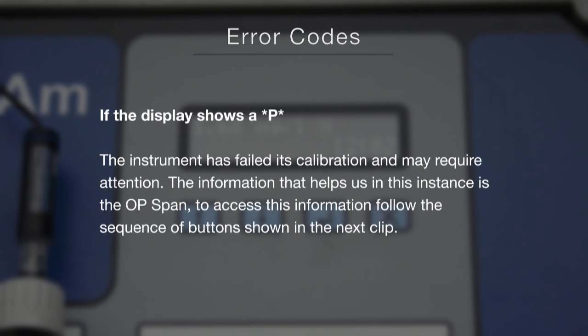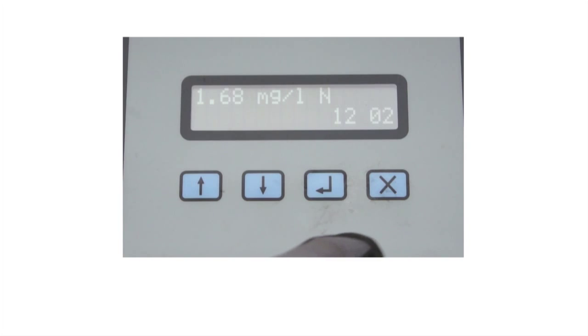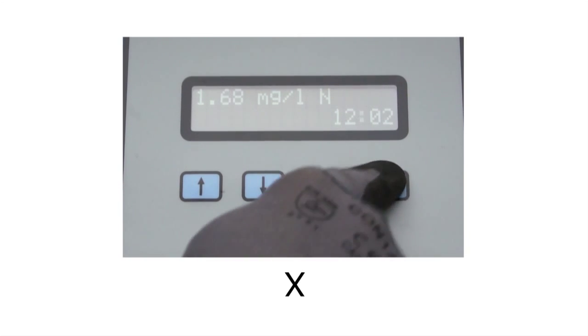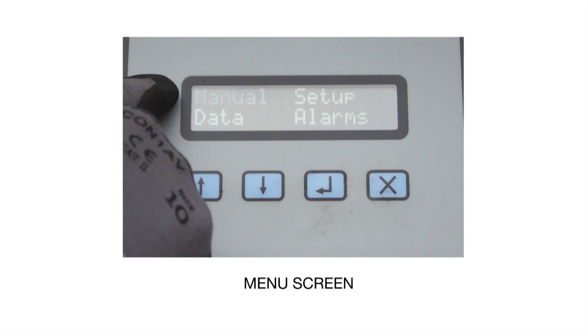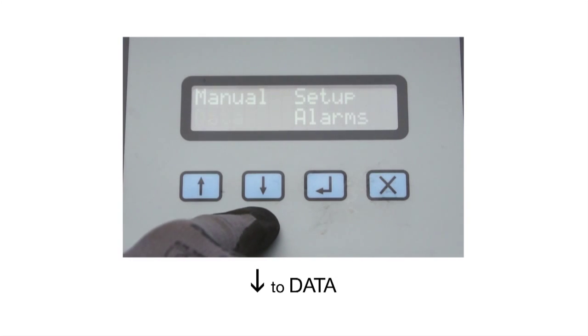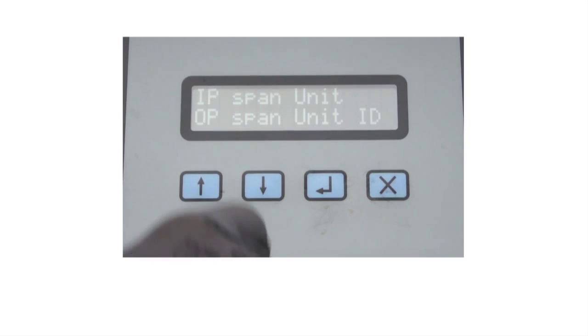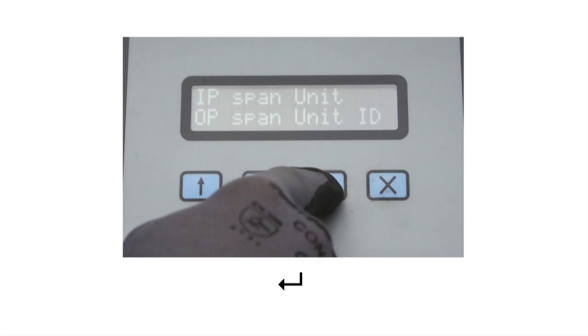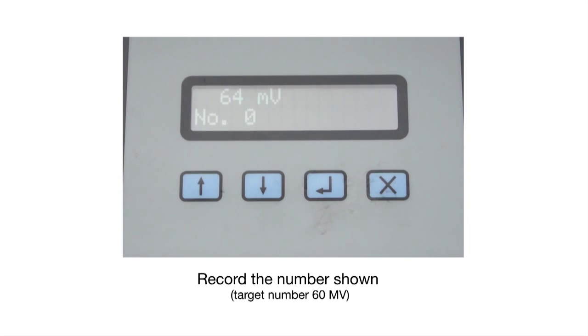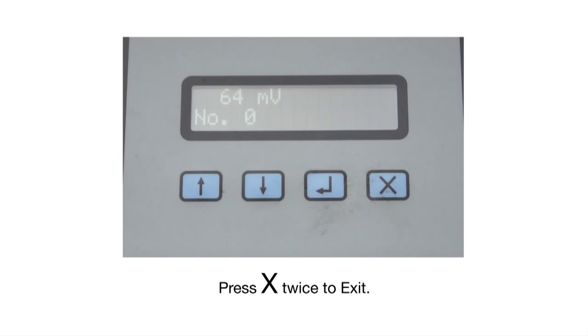If P is on the display, the instrument has failed its calibration and may require attention. The information that helps us in this instance is the OP span. To access this information, follow the button presses shown. Enter, then X. Then the down arrow to data, then enter, then the down arrow to OP span, then enter again and record the number shown. The target number here is 60 millivolts. To exit that menu, press X twice.